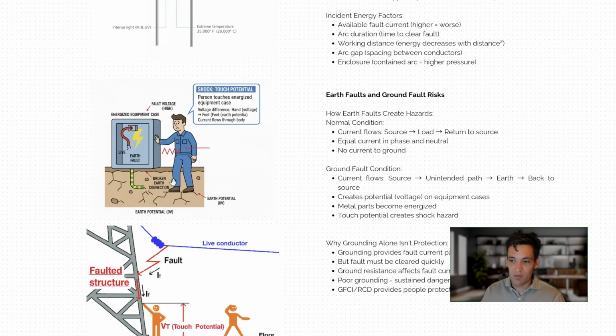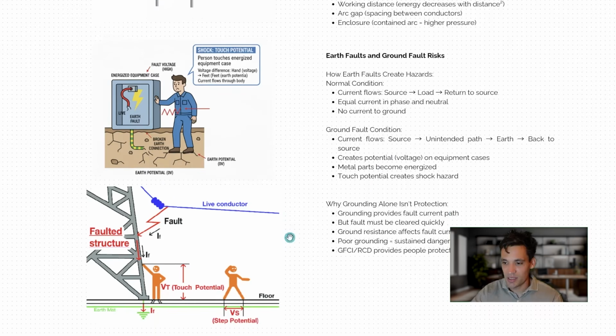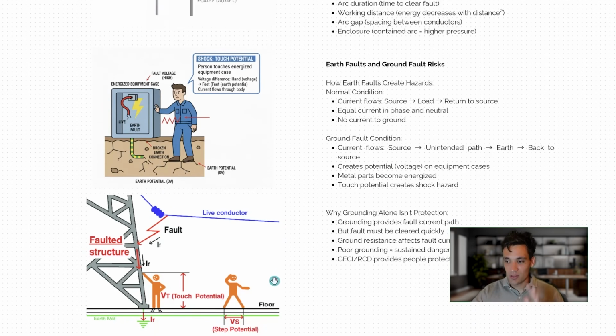So you could have a situation where there's sufficient voltage, or the earth is far enough away from the earth at the transformer to complete the circuit, where there's actually resistance in the earth part. So even if the equipment is earthed, if it gets a huge fault current and you have a tiny 6mm earth, because there's resistance in the earth part, the frame could still have some sort of touch potential. That's referred to as earth potential rise. That's referred to as touch potential, where you have resistance between the frame of a faulted structure and the actual earth.